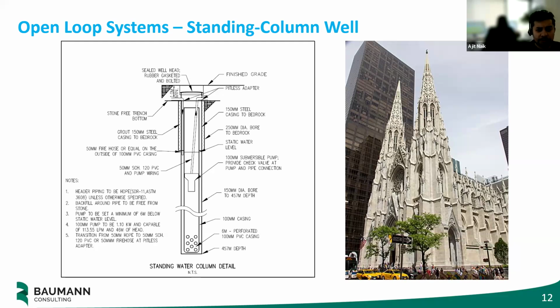There are other places too, and sometimes permitting can be an issue. In Northwest DC, you could do this given the local geology, but you can't permit this type of system there. Just because it sounds like a good idea doesn't mean you won't run afoul of the regulators. In general, open loop systems are much more scrutinized and subject to that type of regulation.